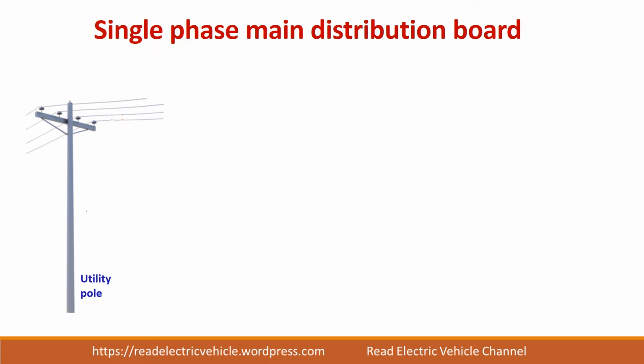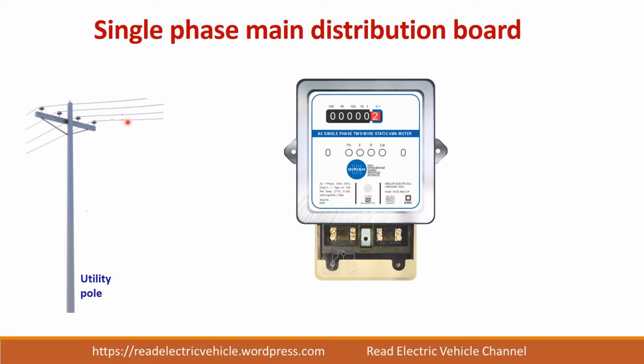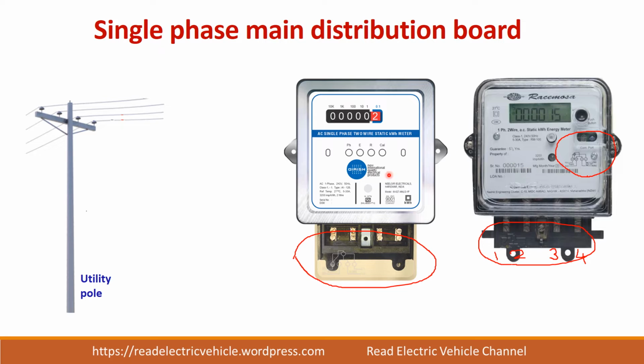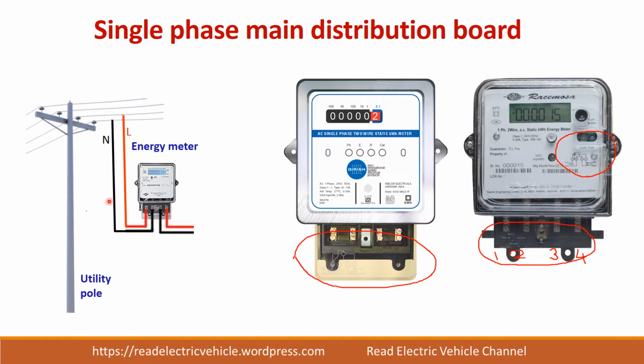Let us see the wiring diagram for the single phase main distribution board. So we have the utility pole. From the utility pole you have to connect the energy meter. Since it is a single phase, we can take this type of meter where we will have 4 terminals, out of which 2 are for input and 2 for output. The energy meter can be any type. Here the terminals will be marked which is input and which is output. So let us connect the energy meter here. One line, that is the phase, and neutral we can take as input, and these two lines will go to the main switchboard.